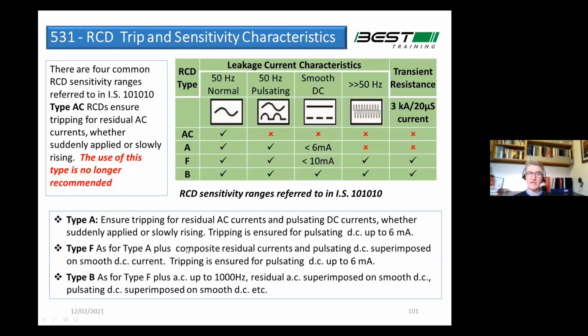I mentioned earlier on as well, type AC RCDs are no longer recommended. In my view, they should really just be taken out, and just say stop using them and just use type A. It's far better. So basically, type AC RCDs go back to the early generation of ELCBs when they were first developed back in the 70s, and they were only designed for detecting sinusoidal earth leakage currents. But of course, in the world we live in now, almost everything we plug in, if it has an illuminated display or a digital display on it, that means you have DC power within the device. And once you convert AC to DC, you get DC leakage currents, either pulsating or direct DC leakage currents, and they have an impact on the operation of the traditional type of RCD.